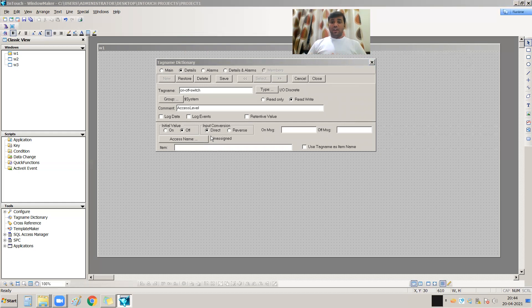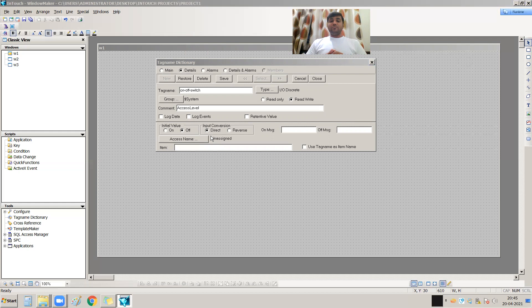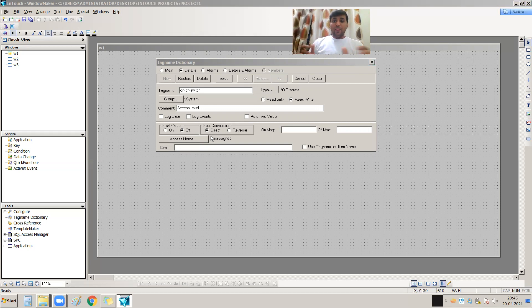If I select IO Discrete — meaning Input/Output Discrete — that tag must have a connection with the PLC. It has to be addressed according to the PLC address. That means the On-Off Switch tag has a particular address in the PLC, and that address must be mapped to this tag.